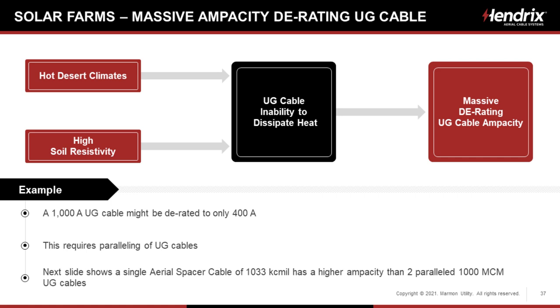I said before that when we have underground cables at a lot of these solar facilities, we have massive ampacity derating of that underground cable. And so why do we have that? Well, if you see on the top left there, we've got hot desert climates, and they get quite hot. We have design goals that we have to design for 45 C ambient, and the ground is hotter. And then we have high soil resistivity. There's no ability to dissipate heat into the surrounding soil. That soil resistivity, in some cases, is infinity, which leads to underground cable inability to dissipate the heat, which ultimately leads to massive derating of underground cable ampacity.